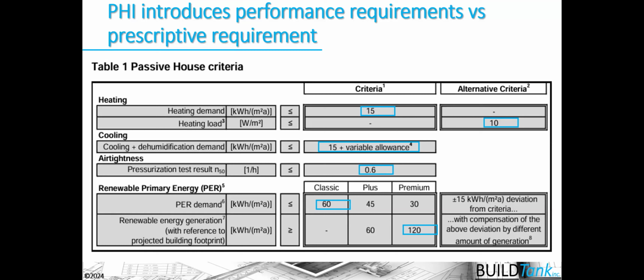So when we go through these Passive House criteria, we see that the heating demand cannot exceed 15 kilowatt hours annually, or 10 watts peak demand per square meter of usable living space. And the cooling demand roughly matches the heating demand with an additional climate-dependent allowance for dehumidification. Now, in our climate zone here in Colorado, we don't need a lot of dehumidification, but what we're seeing in other climate zones is that we not only have to have cooling, but we also have to have separate and independent dehumidification systems in these tighter, well-insulated homes there. Air tightness has a maximum threshold, as I said before, of 0.6 air changes per hour at 50 pascals of pressure.